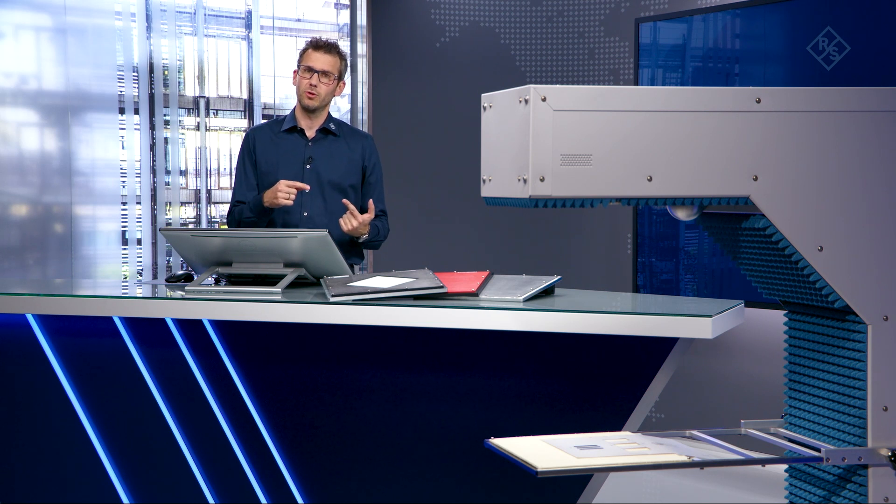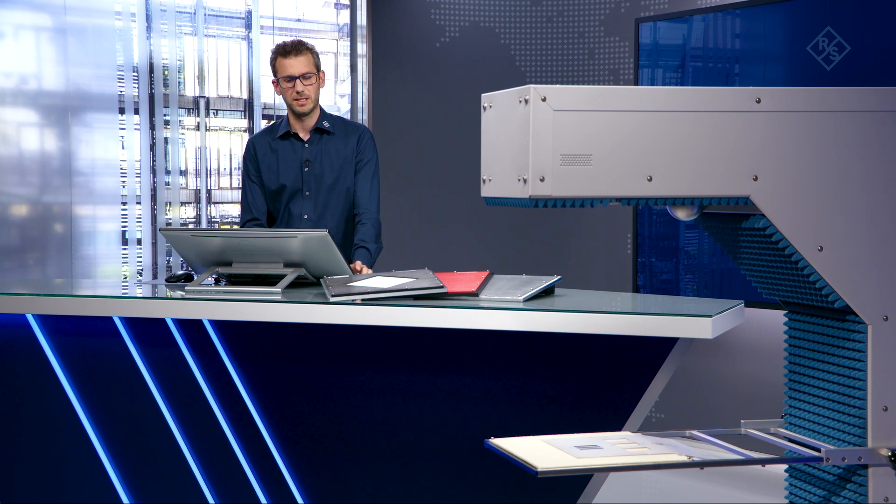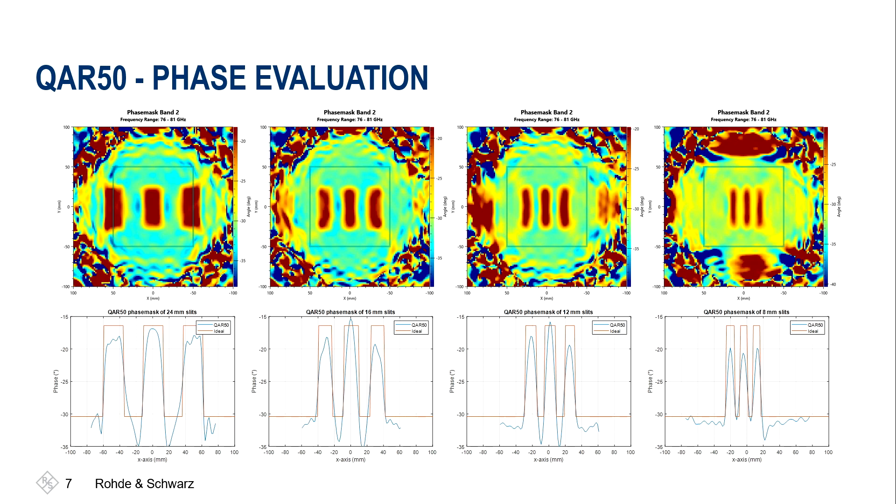How does that look with the different cutouts that we have prepared? This is depicted on that slide showing a summary of the different measurement results. Again, the phase mask image on top and the two dimensional representation of the center on the bottom. If we have bigger cutouts, for example, the slits with 24 millimeters on the left, we can see we are pretty close to the ideal behavior. And the smaller the slits get, the smaller also the phase gets that we measure with the QAR50. On the right hand side, again, the border case where we have the 8 millimeter slits, which is roughly the resolution of the instrument.